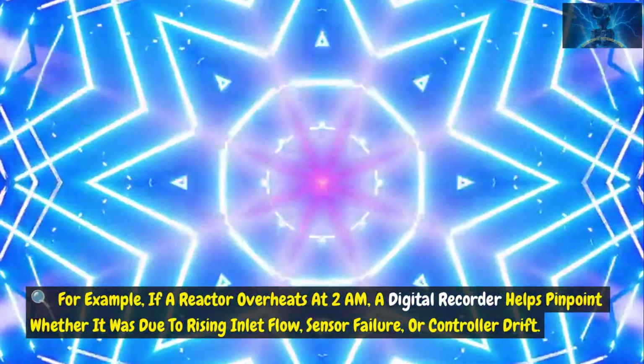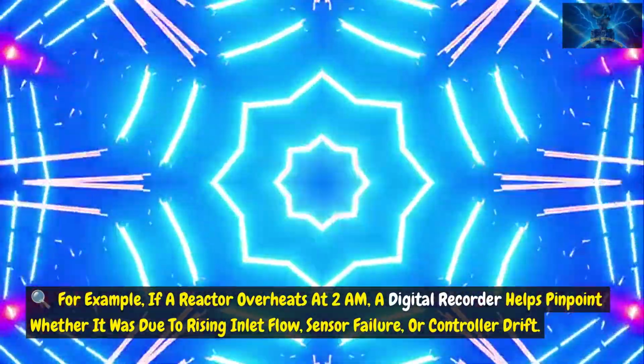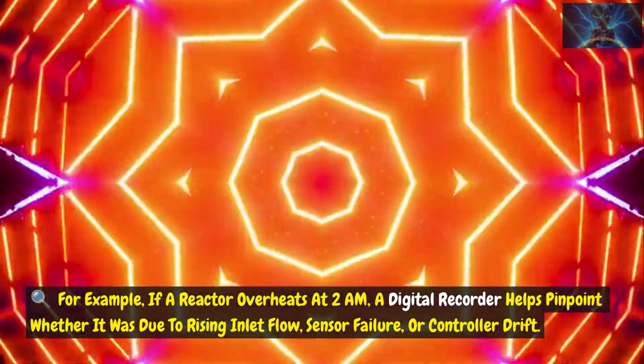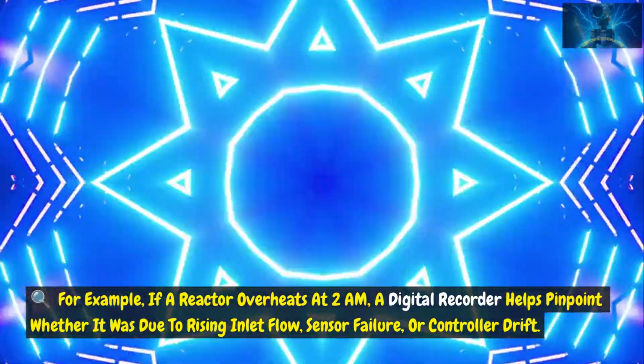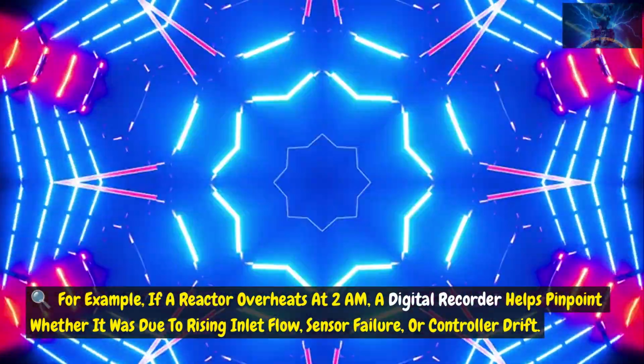For example, if a reactor overheats at 2 a.m., a digital recorder helps pinpoint whether it was due to rising inlet flow, sensor failure, or controller drift.